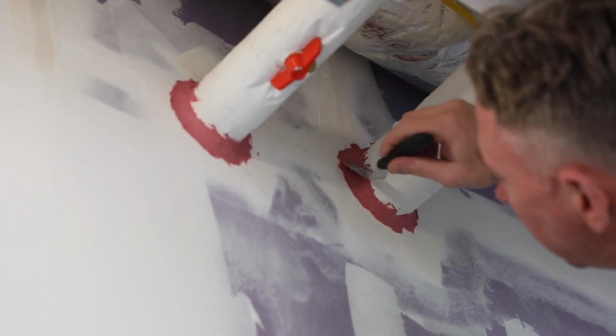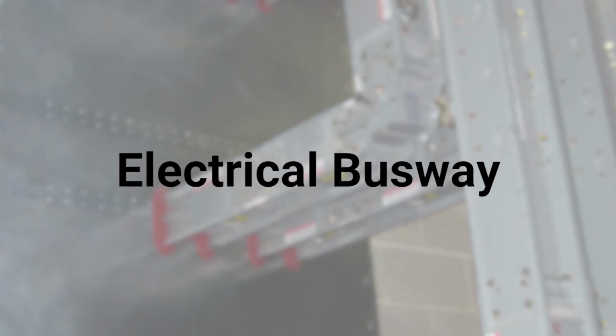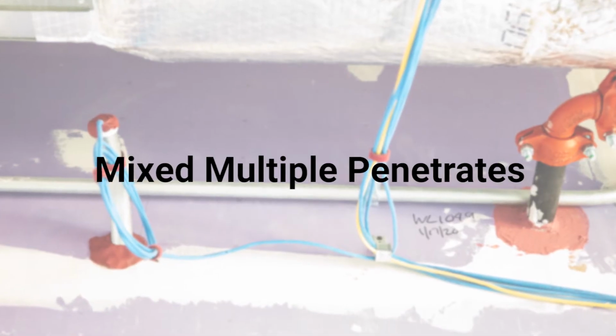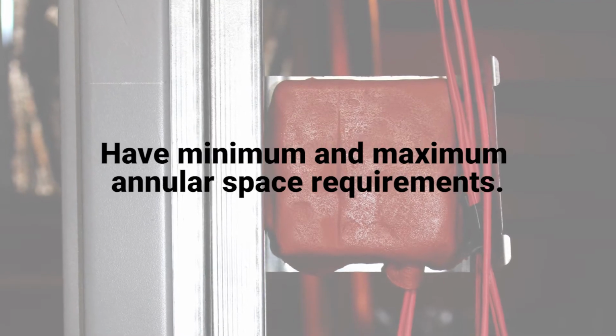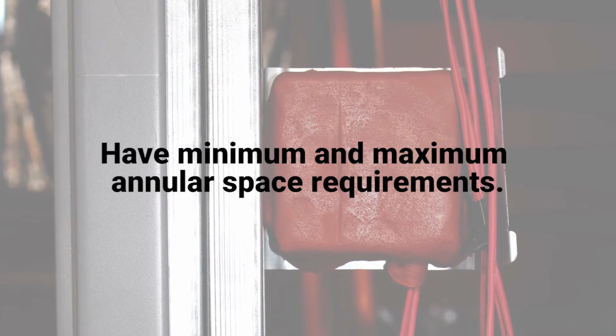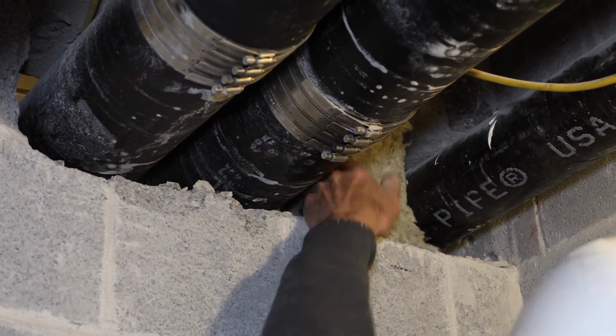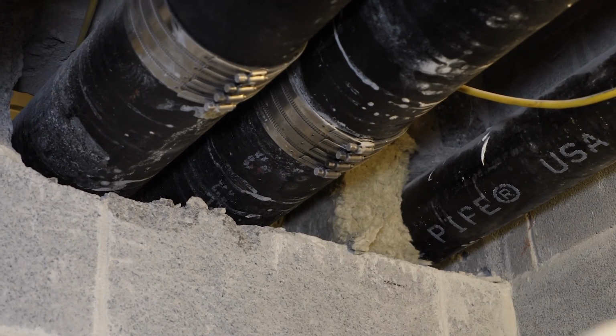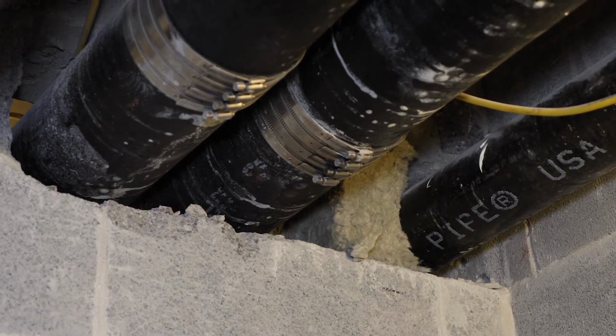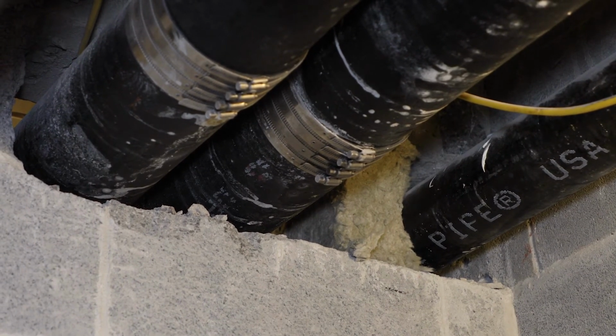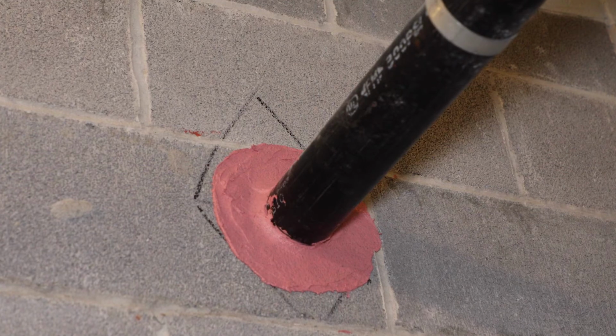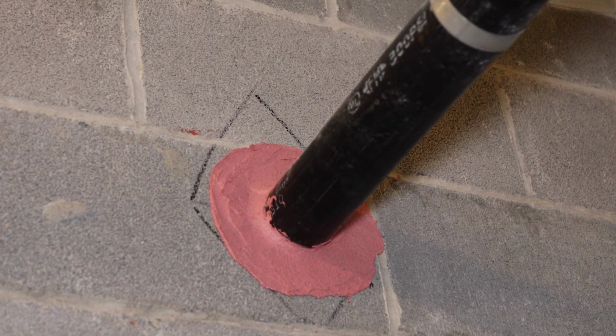These penetrations, along with others such as cable trays, busway, ducts, and multiple mixed penetrants, will always have minimum and maximum annular space requirements. Penetrations with larger annular space may require forming, packing, or backing materials such as mineral wool. However, it's worth noting that some systems allow for this material to be optional.